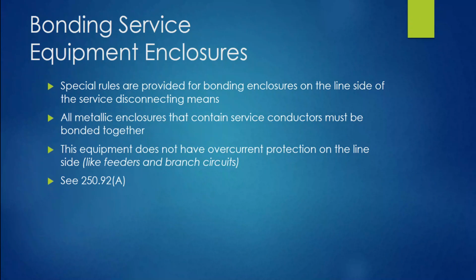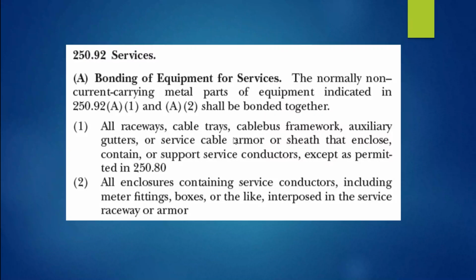Now, this equipment does not have overcurrent protection on the line side. We've talked about it. Unlike what you have on the load side for feeders and branch circuits, where you can trip an overcurrent protective device using a main bonding jumper, here we're on the supply side, and they're not main bonding jumpers, but they are tying all metal parts together. They are taking a chance that when you do so, and you size these conductors and make the connections properly, you might clear a fuse on the primary side of the utility. Can't guarantee it, but you might. We don't govern that in the NEC. So here's what the code says.